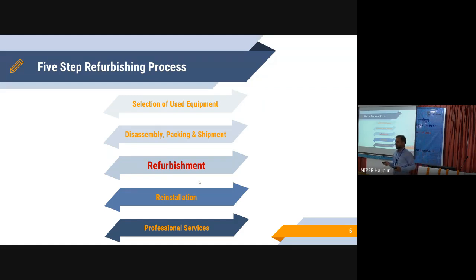You see, the party who is doing the refurbishment, they have to identify which instrument is best suited for the refurbishment, and when they are performing refurbishment, they have to consider the type of medical device, its history, means service record, service history, configuration, and the condition in which it was being used, and the availability of the original spare parts supplied by the original equipment manufacturer.